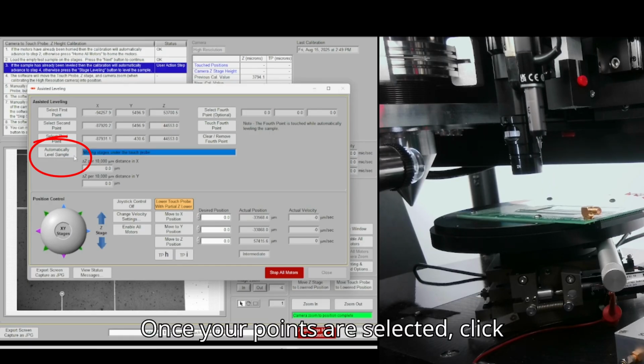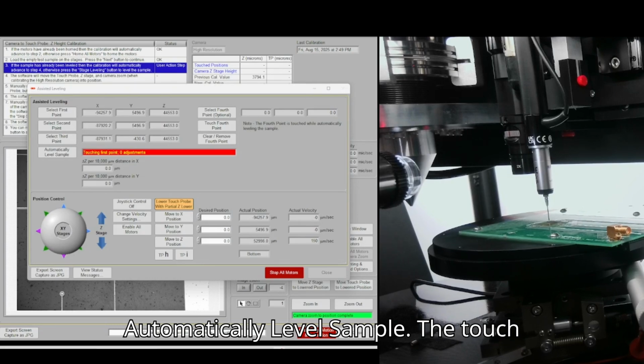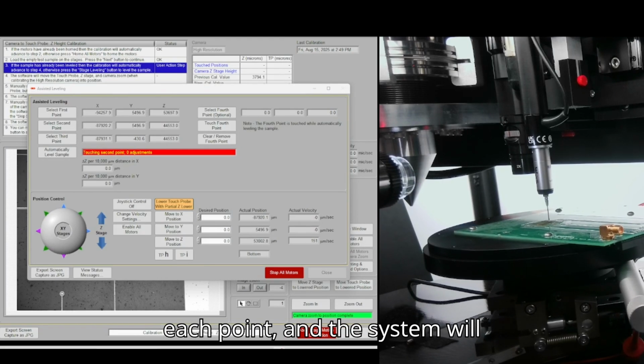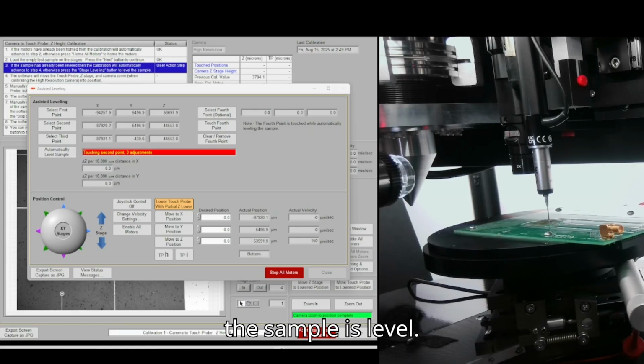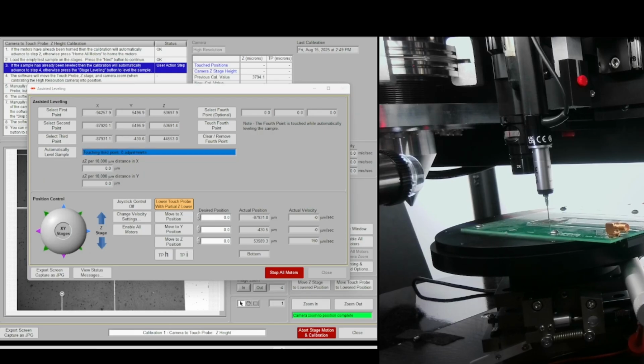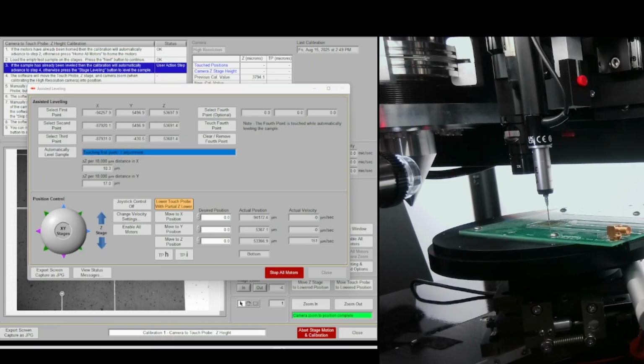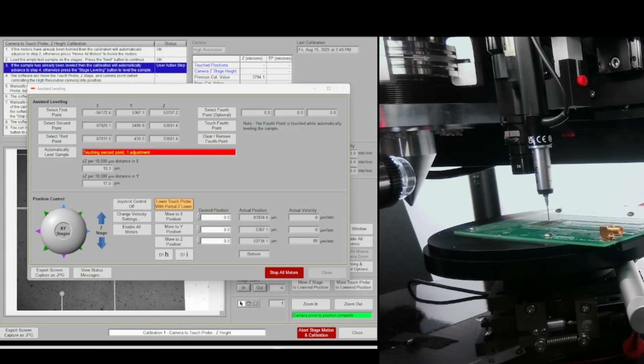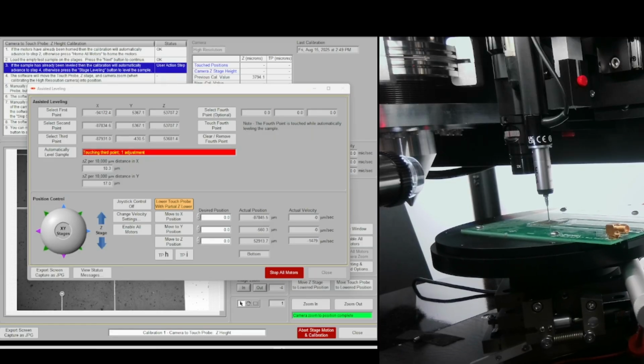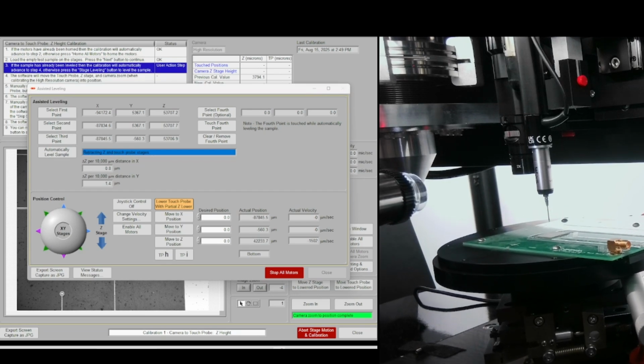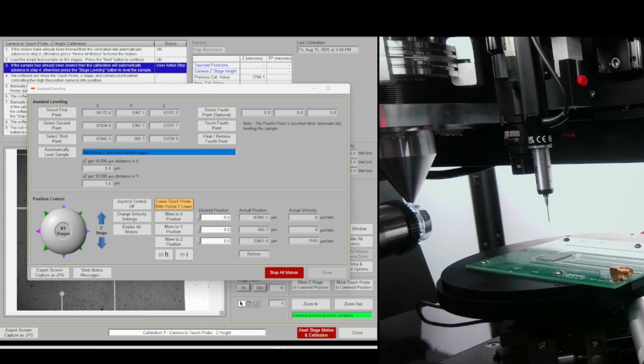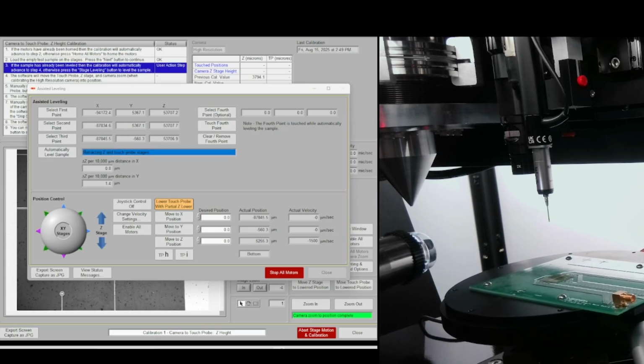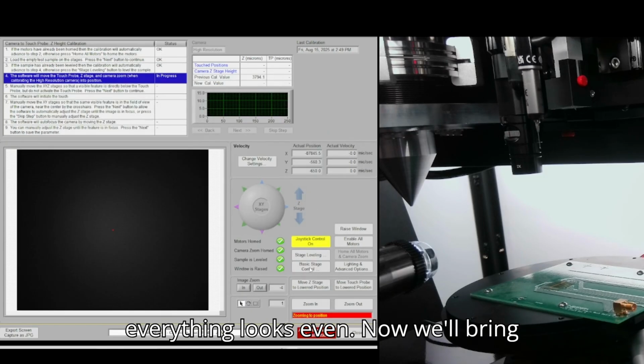Once your points are selected, click Automatically Level Sample. The touch probe will measure the surface height at each point, and the system will automatically adjust the stage to ensure the sample is level. When leveling is complete, verify that everything looks even.